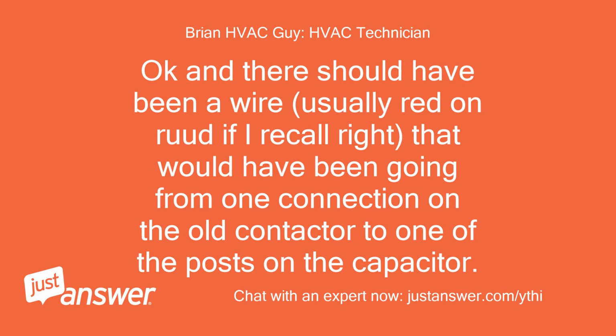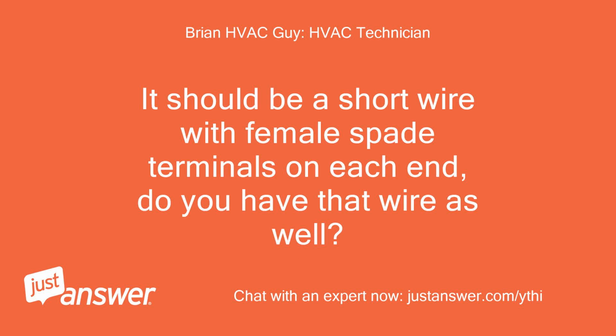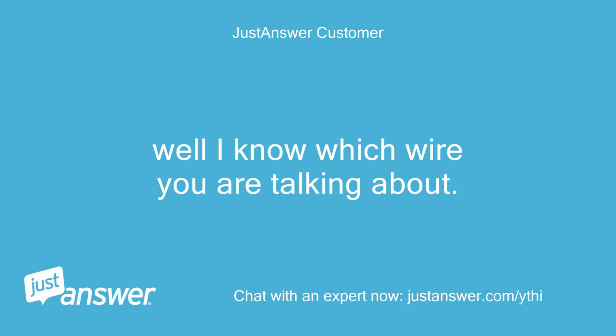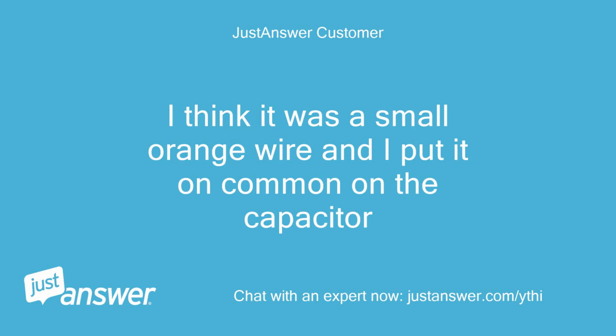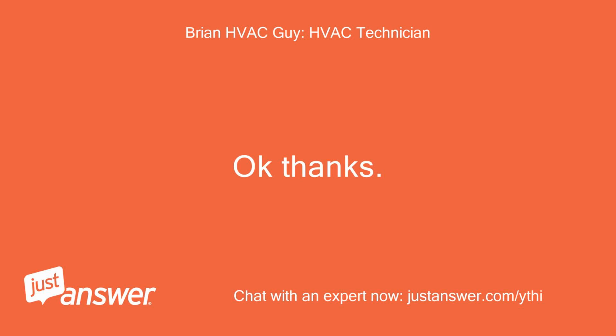Okay, and there should have been a wire, usually red on Ruud if I recall right, that would have been going from one connection on the old contactor to one of the posts on the capacitor. It should be a short wire with female spade terminals on each end. Do you have that wire as well? Well, I know which wire you are talking about. I think it was a small orange wire and I put it on common on the capacitor. Okay, thanks.